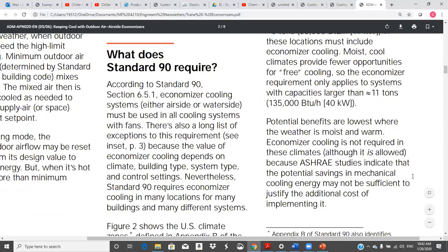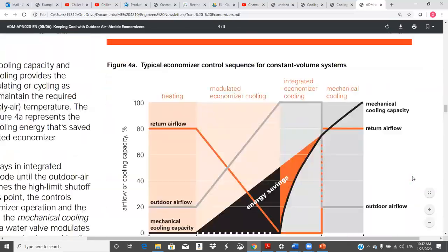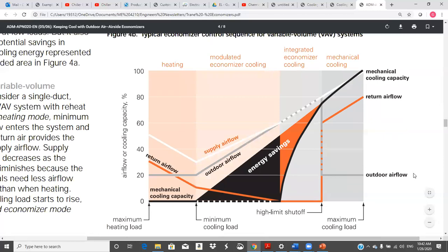So it's a similar picture, but the story changes a little bit. Now, let's see if I can remember the story. I don't know if I can or not, but let's take a look at it. So again, same basic setup, really cold, really hot. Mechanical cooling is off, up until here, same kind of a deal. So let's look at what's happening. This is the cold outside air, and that is again set by the ventilation code. When it's cold and we're in heating mode, we don't want any more of that stuff than we have to have.